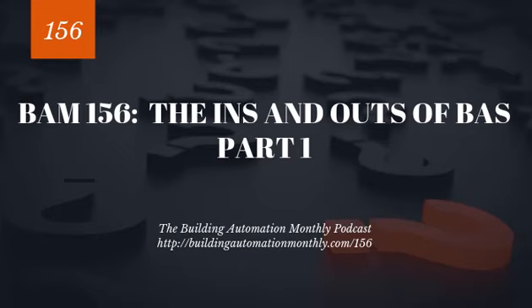Bit number 2 means room 101 or means cooling, and bit 3 means heating, and bit 4 means mechanical cooling. So that way, as these different bits are set on, you now have context. That is a multi-state value. That is an enumerated value.